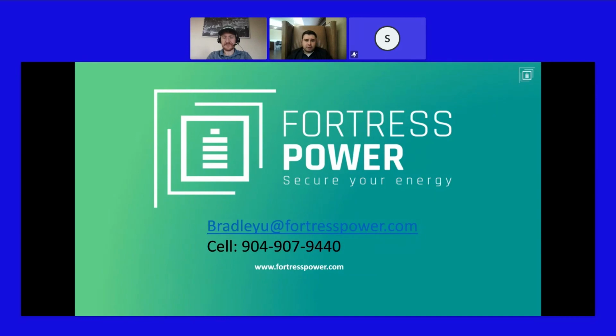In terms of the extra solar going to the batteries, 1.6 is the magic number to remember. For example, you have solar panels and they produce a lot of energy. You have a 7.6 kilowatt inverter. The 7.6 kilowatt inverter can send 7.6 kilowatts to the load, and then up to 60% of that 7.6. Let me calculate what that is. Okay, so 4.6 kilowatts it can send to the batteries. Whatever the inverter rating is, it can provide that much power to the load, and simultaneously 60% of its power rating to the batteries to charge them.